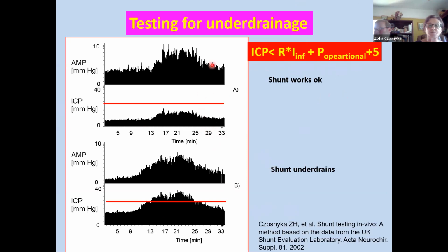We've got two examples, of a properly functioning system and of underdrainage. Intracranial pressure during infusion never exceeds the critical value, so we can conclude this valve is draining properly. For this system, during infusion, intracranial pressure exceeded the critical value significantly, so we may conclude that the valve is underdraining or maybe even blocked distally.